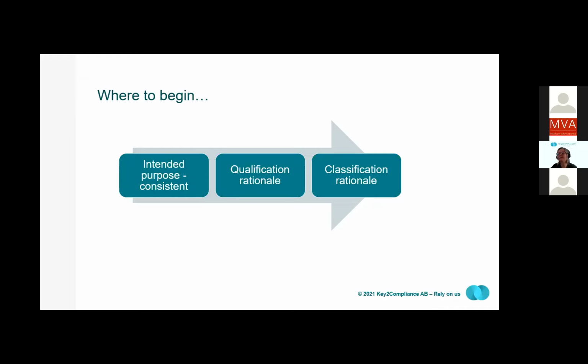To establish these 3 points in the beginning, you will save a lot of time going forward, since other documentation such as clinical evaluation, device description, etc., are depending on the classification and intended purpose. To most of you, this might seem obvious, but I have seen several examples of projects where the intended purpose is not established until later, and how it causes big problems with the update of other sections of the technical documentation. And you would also lose a lot of speed in your project.